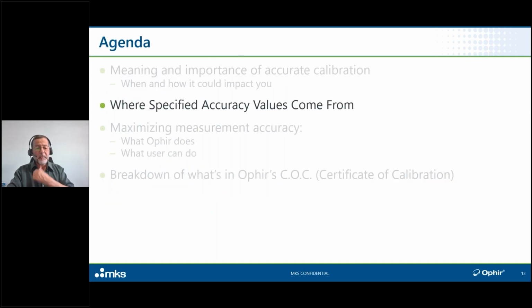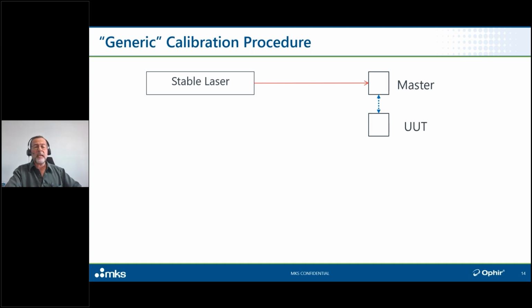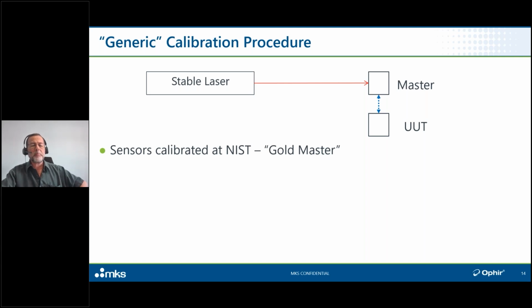Where do the specified accuracy values come from? So let's just quickly get a very, very general idea of a generic calibration procedure. We start with a perfectly stable laser, or as close to perfectly stable as we can manage. We have what we call a master sensor. We periodically send representative sensors from various product families of ours to NIST for them to calibrate. Costs a bomb, takes a long time. We get them back. We call that our gold master.